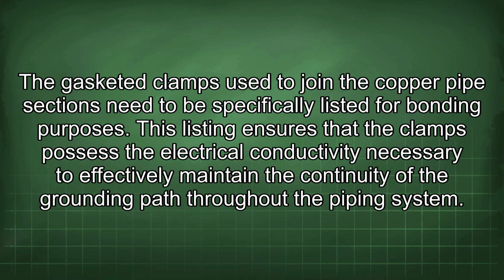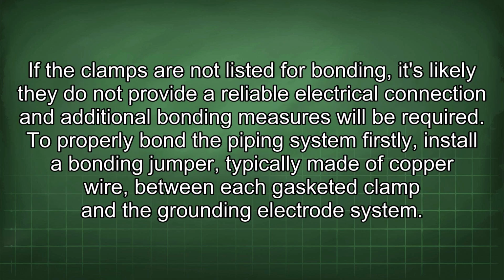The gasketed clamps used to join the copper pipe sections need to be specifically listed for bonding purposes. This listing ensures that the clamps possess the electrical conductivity necessary to effectively maintain the continuity of the grounding path throughout the piping system. If the clamps are not listed for bonding, it's likely they do not provide a reliable electrical connection and additional bonding measures will be required.